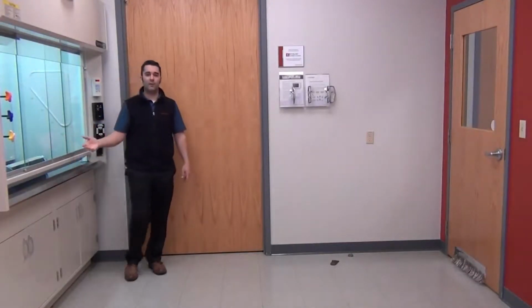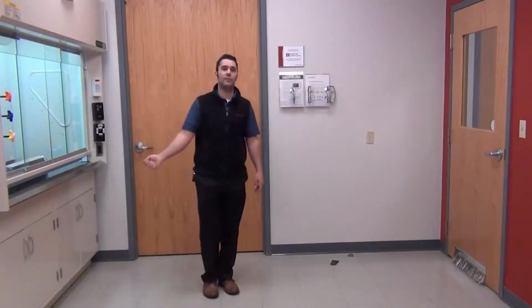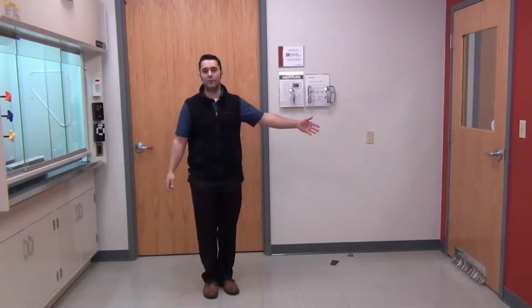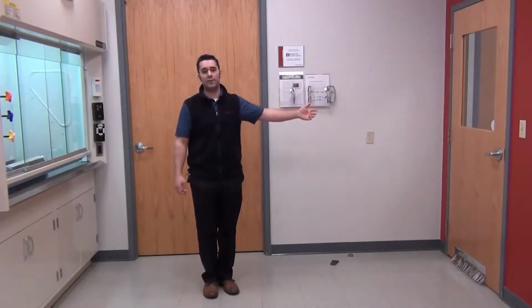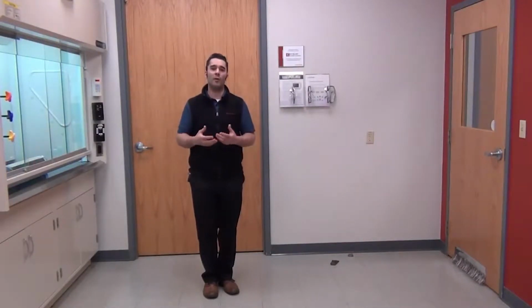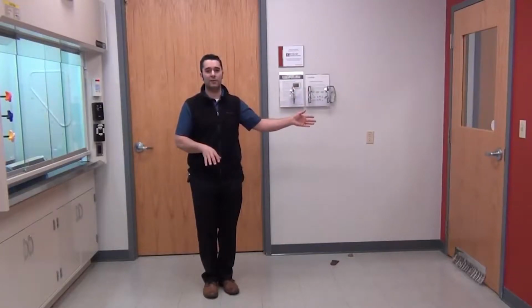So if I had a spill in my fume hood, or if I dropped something on the floor and closed my sash very quickly, now those chemicals could have just washed out into the corridor, contaminating occupants inside the corridor as well as the adjacent spaces across the hallway. So that's why when you're looking at pressurization as a whole in a wet chemistry lab, all of the devices inside the lab should be at a 1 second speed of response to guarantee pressurization inside this space is maintained no matter what happens, as well as the adjacent spaces outside the corridor. Everything has to balance out to make sure that the entire system doesn't have cross-contamination and that you're going to have the most accurate and stable system that you can.